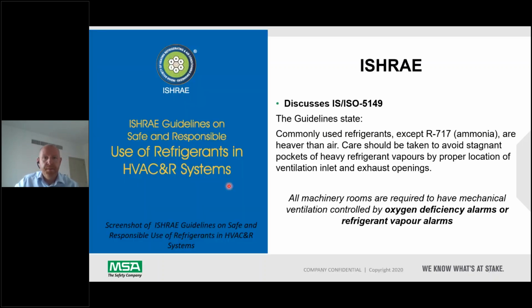This is just a screenshot of the front of the ISHRAE guidelines. It discusses the international standard, ISO 5149, and it states that all machinery rooms are required to have a mechanical ventilation system controlled by oxygen deficiency alarms or refrigerant vapor alarms. An oxygen deficiency alarm is an oxygen detector. So if the mass of refrigerant in the room is more than the oxygen, the levels of oxygen in the room will start to decrease and become dangerous for people to breathe in there. But at this stage, it's really too late. So it's much better to install a leak detection system that detects the actual refrigerant at a very early stage than an oxygen deficiency system.